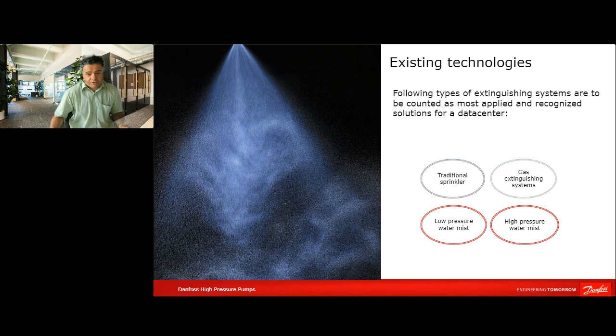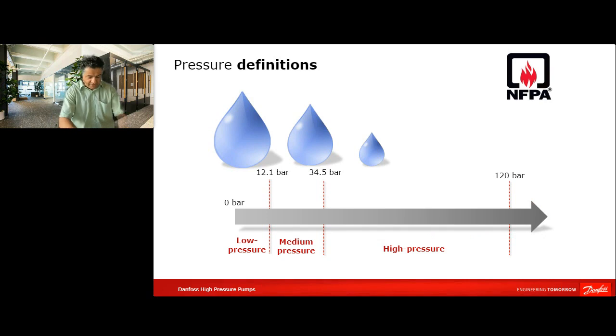Talking about the pressure, there are clear definitions in the standards documents and regulations. For example, the National Fire Protection Association defines the pressure ranges like you can see in this slide. Up to 12.1 bar is defined as low pressure. From 12.1 bar to 34.5 bar, we talk about medium pressure, and above 34.5 bar it is defined as high pressure. The area where our pumps are working is around 120 bar. It can be lower and it can be higher, but we talk about system pressure, internal pressure, not the pressure of water which comes out of the nozzle. So don't worry about that.